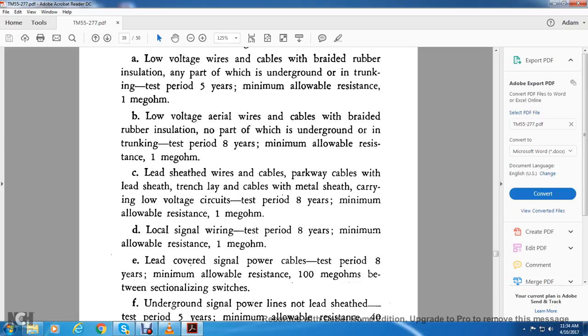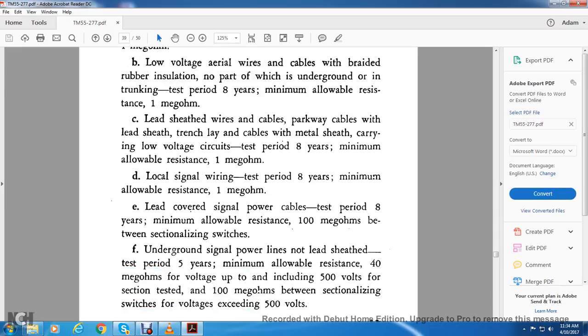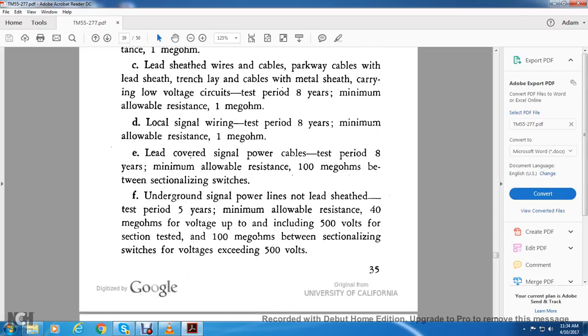C. Lead sheathed wires and cables, parkway cables, and lead sheathed trench lay cables with metal sheath carrying low voltage circuits: test period 8 years, minimum allowable resistance 1 megohm. D. Local signal wiring: test period 8 years, minimum allowable resistance 1 megohm. Lead covered signal power cables: test period 8 years, minimum allowable resistance 100 megohms between sectionalizing switches.